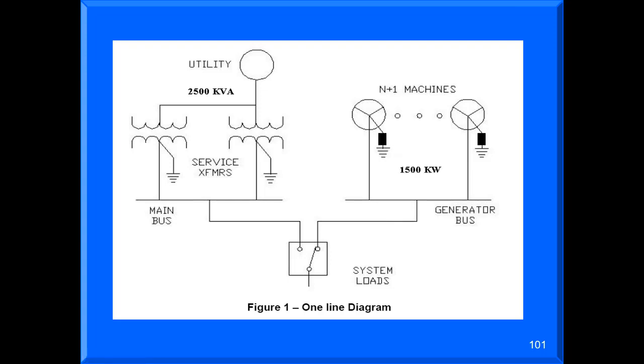Okay. You've got two options. The first thing I can do: all the protective relays now have more than one set of protective curves. Like in the Multilin, I can give you six different sets of curves. So where I could have the ground circuit for this, when this switch is over, I could automatically switch to a second set of group settings and protect for the 400 amp.